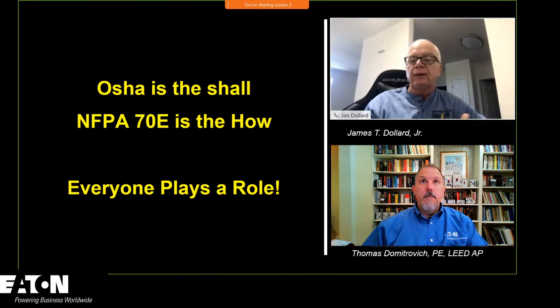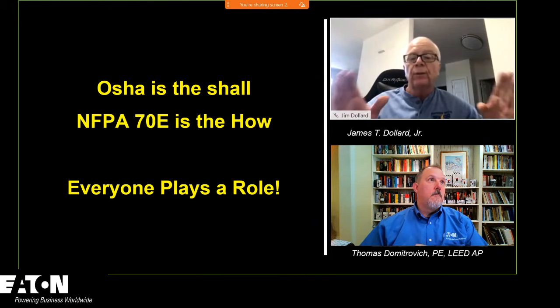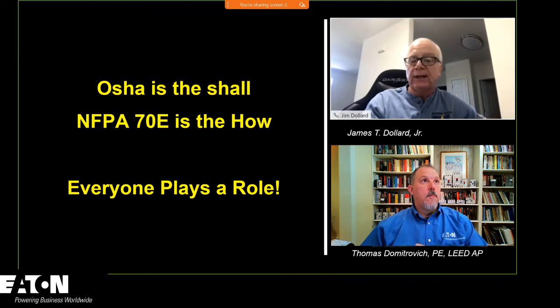I do see a question: NFPA 70 arc flash labels, are they specifically looked for and required? That would be the generic label in 110.16(a), yes. It requires all panel boards, switchboards, motor control centers, etc., anything other than dwelling units, to be marked with a general warning label saying arc flash hazard. But there is no general requirement in the NEC that you label in a manner like we do with 70E. The only time you get there is service equipment at 1200 amps.